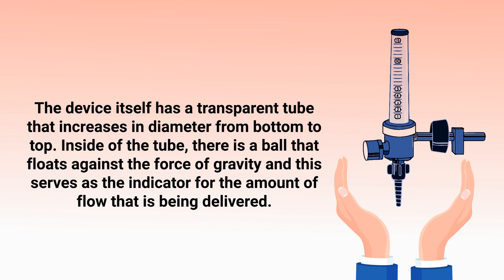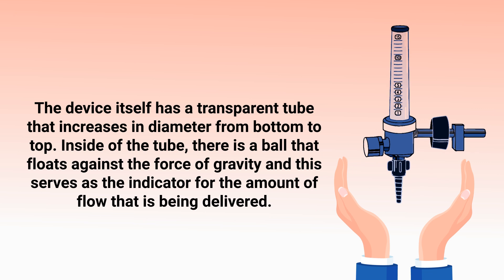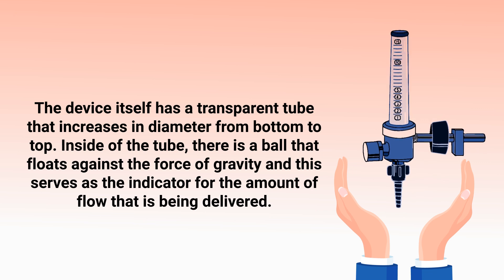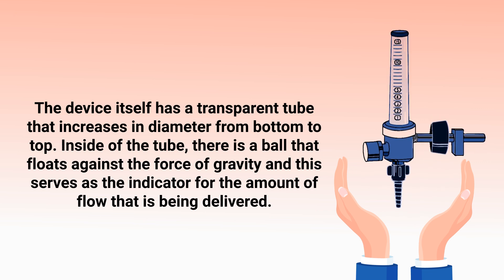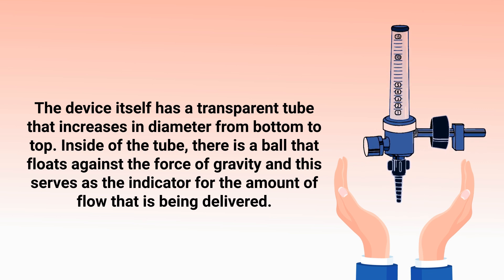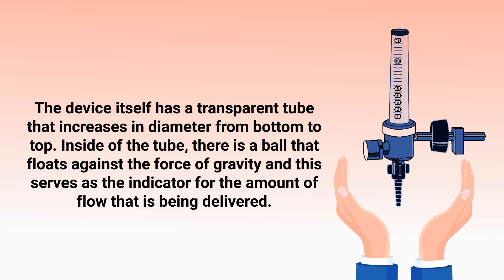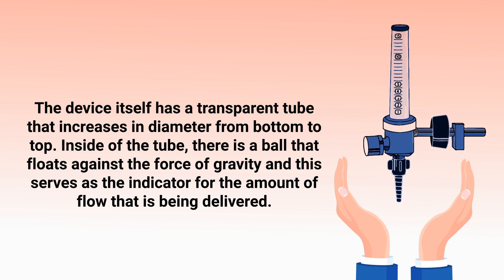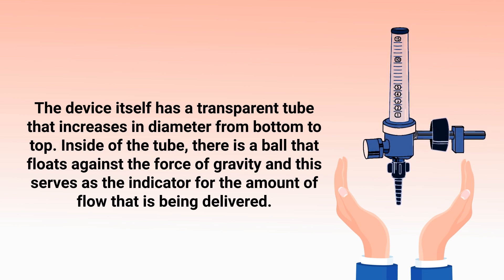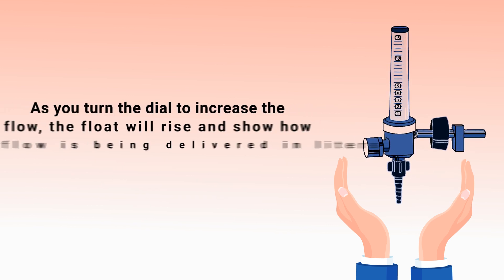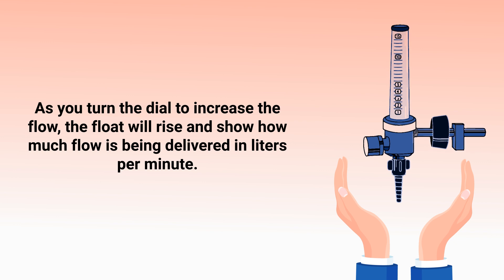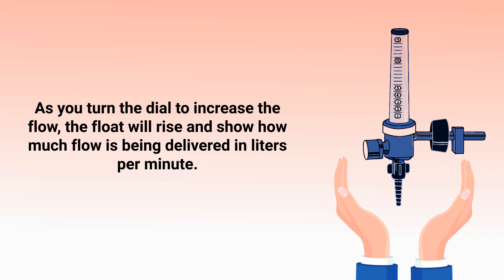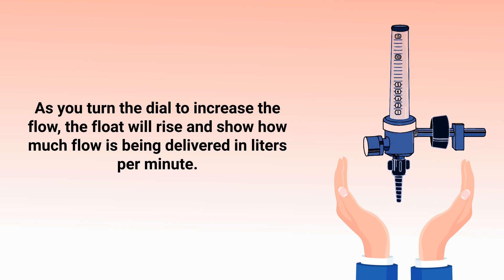The device itself has a transparent tube that increases in diameter from bottom to top. Inside of the tube there is a ball that floats against the force of gravity, and this serves as the indicator for the amount of flow being delivered. As you turn the dial to increase the flow, the float will rise and show how much flow is being delivered in liters per minute.